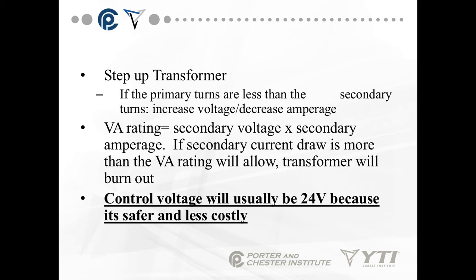The VA rating, or the volt amp rating, is the secondary voltage multiplied by the secondary amperage. So if the secondary current draw is more than the VA rating will allow, the transformer will burn out. You're going to see transformers that basically say 40 VA, 60 VA, 50 VA. That's volts times amps. Control voltage will normally be 24 volts because it's safer and less costly. So most of the transformers you're working with for control voltage is going to be 24 volt, and most are 40 VA, but you can have to go higher.